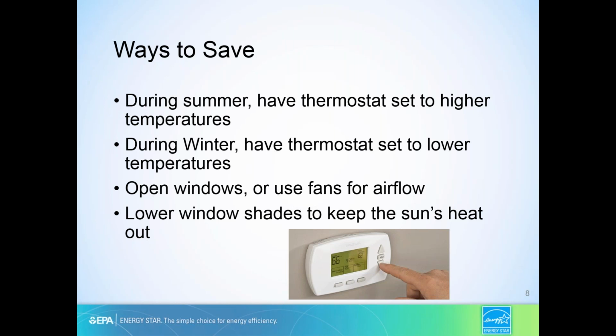Yeah, that's a really good point. One of the things that we do with some of the buildings that I work on is we have setbacks. Instead of totally turning off the air conditioning system when the building or the space is not occupied, you set it back a few degrees warmer, so it's creeping up for several hours until that building is reoccupied, and then it can come back down to the desired set point. Right, and this takes place in both summer and winter. In the winter, obviously, we keep the temperatures in the spaces cooler.